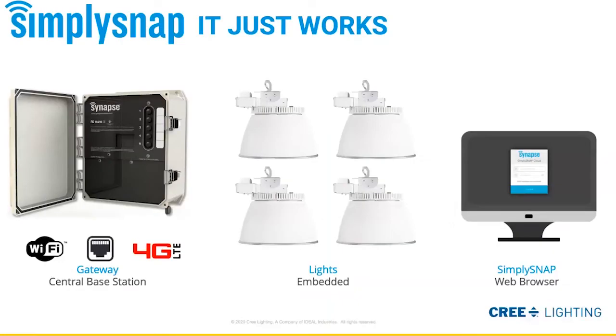So as we start to wrap things up, let's talk about those components that are involved in a SimplySNAP system. What would a customer purchase and how would it work? Every SimplySNAP install, you're going to have at least one gateway and some number of lights. Each gateway typically manages about 500 lights, and those lights could have sensors connected to them, motion sensors, some may or some may not.